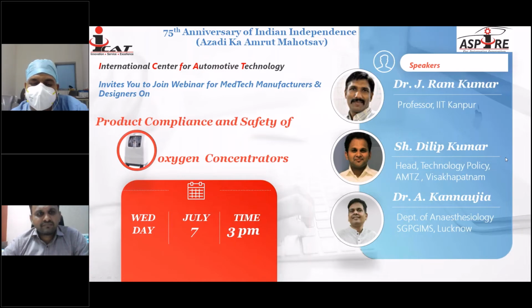For COVID patients, oxygen concentrators can be used for home care for mild to moderate cases where the oxygen requirement is not very high, in the range of 4-5 liters per minute. But during selection of an oxygen concentrator, one must see what concentration is being given at maximum flow. If someone buys a 5-liter oxygen concentrator, and it says it's giving 93%, 90 plus minus 3%, at 1 liter, but at 5 liters it's giving only 30-40%, then it's not of much use.